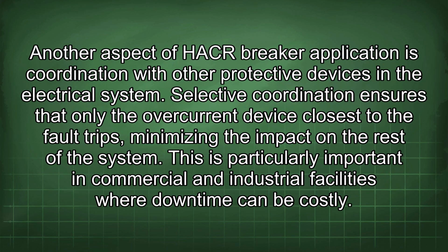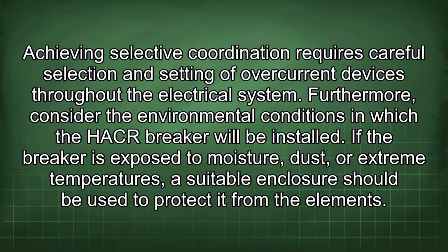Another aspect of HACR breaker application is coordination with other protective devices in the electrical system. Selective coordination ensures that only the overcurrent device closest to the fault trips, minimizing the impact on the rest of the system. This is particularly important in commercial and industrial facilities where downtime can be costly. Achieving selective coordination requires careful selection and setting of overcurrent devices throughout the electrical system.